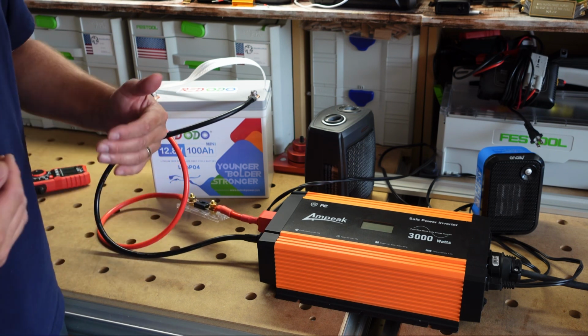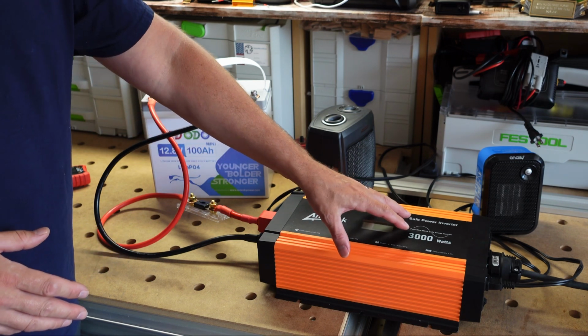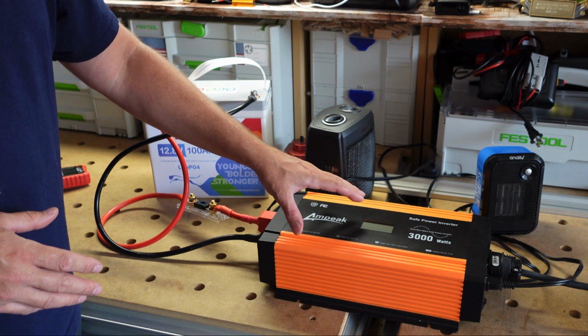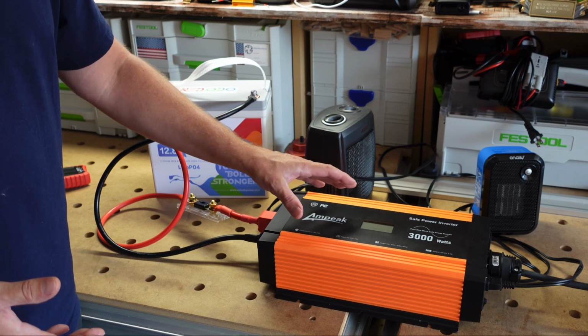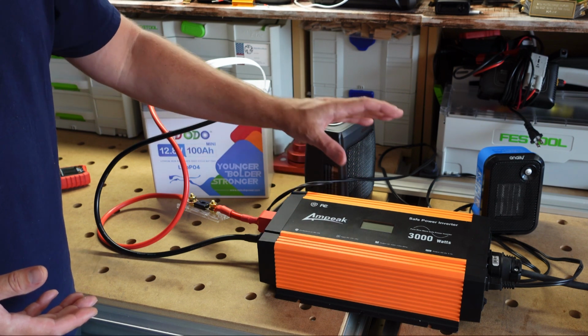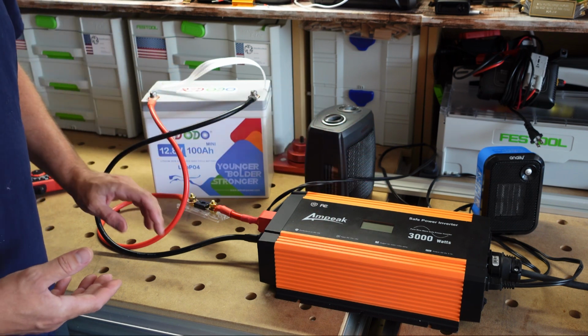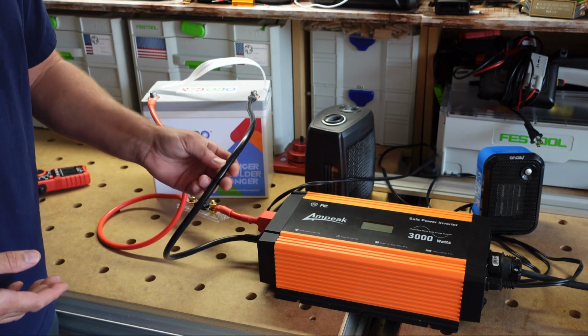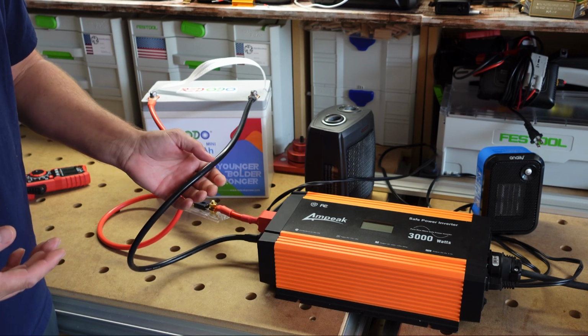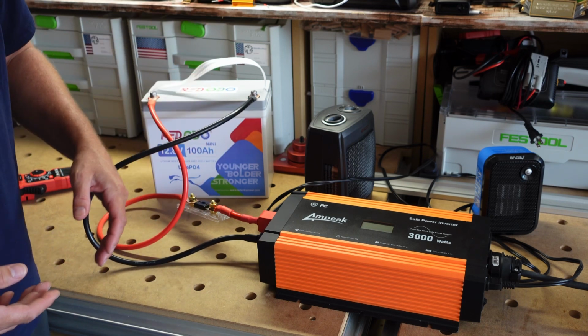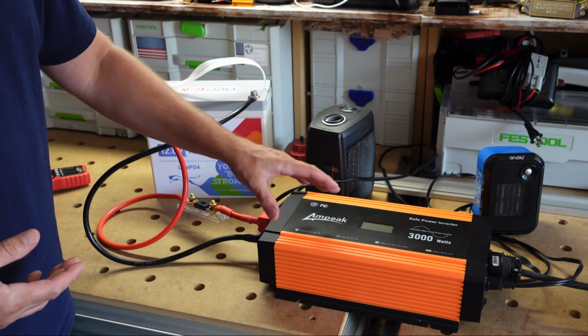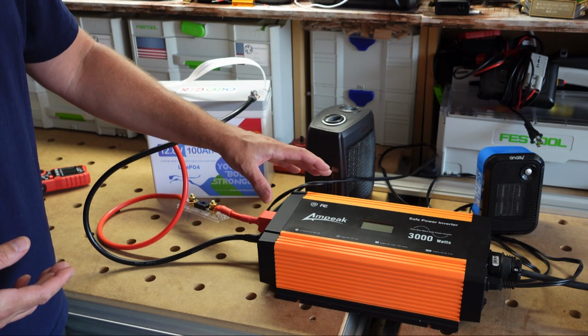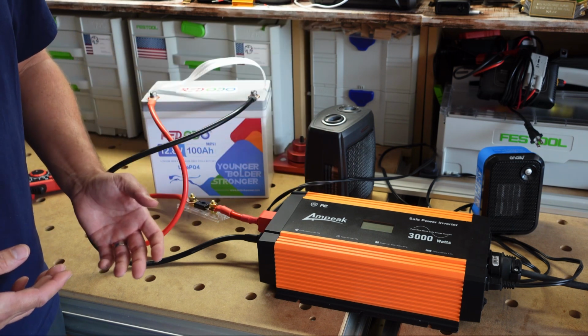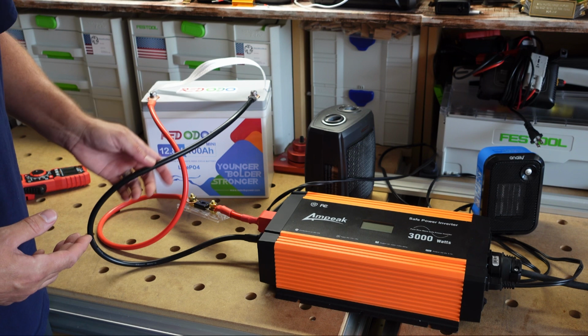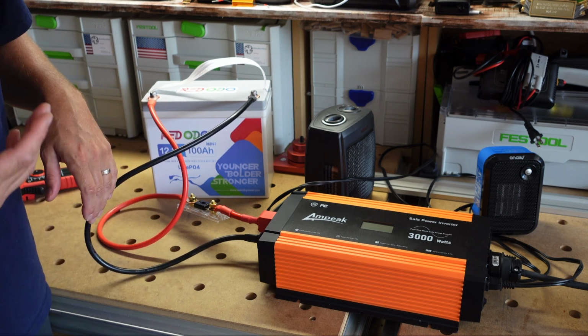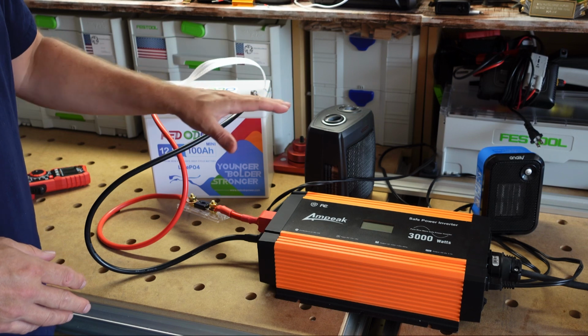Now folks, in my opinion, this is why some of these really high wattage 12 volt inverters really aren't that good of a choice, because 3000 watts takes so many amps to push through these cables. You're going to have to use 1/aught, 2/aught, 3/aught cables to be on the safe side, and that's really, really expensive, and the cables get hot. It's just a lot of watts on a 12 volt system. If you're going to be running 3000 watts, I recommend going to a 24 volt system to cut those amps in half, which means you don't have to get such big cables, and to me it's safer. But nonetheless, let's wrap up the testing on this inverter.